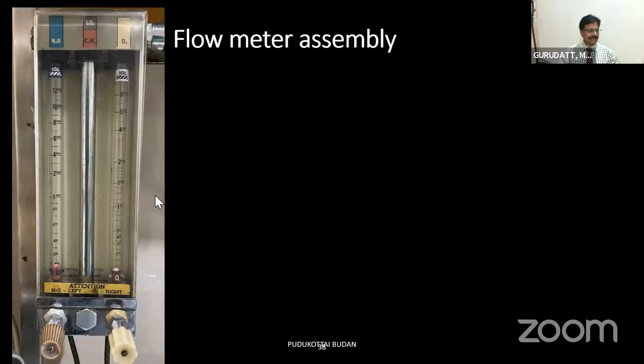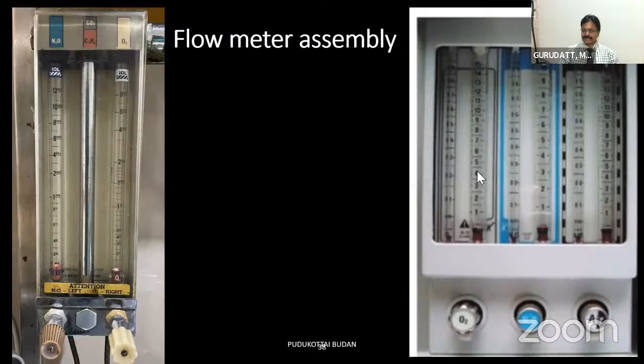Now the flow meter assembly, you have seen in many of the older anesthesia machines. We have the flow meters, and each gas has a single flow meter in the older machines. With this single flow meter, there used to be a lot of difficulty in maintaining accurate flows for the low flow anesthesia technique. So presently, we have 2 flow meters for each gas in modern workstations. A separate flow meter up to 1 liter is for low flows, so you can accurately set even the low flows, and for higher flows, you can use the second flow meter. They are in series, so it's a continuation of gases. That's how in modern workstations, we have 2 flow meters for each gas.